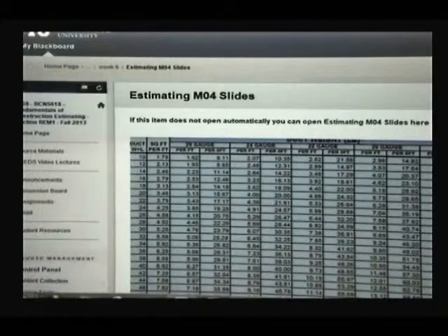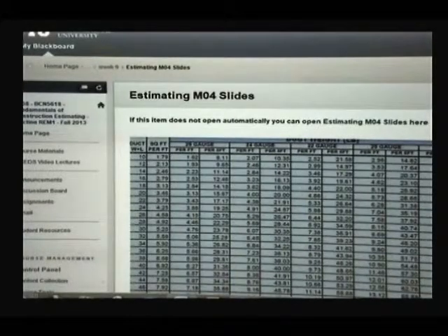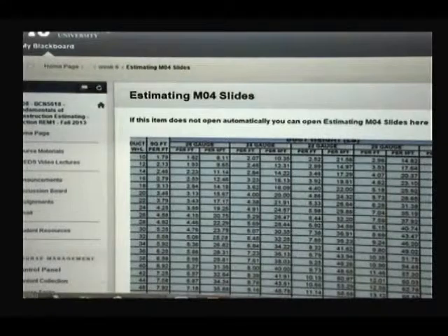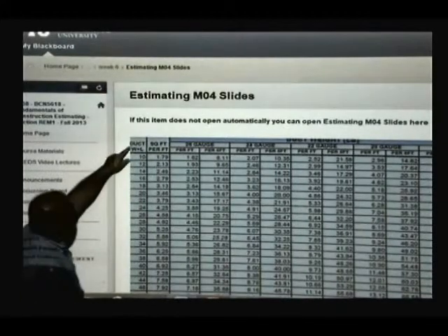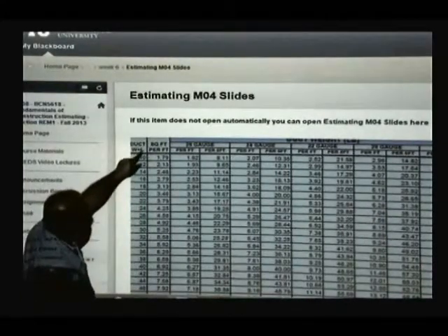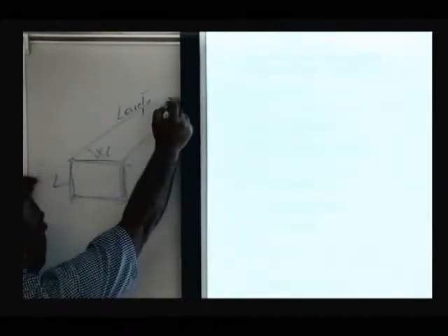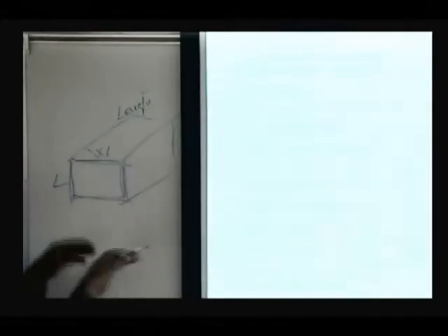So basically we have these two dimensions they call W and L, right? So we want to add W plus L, and then the table considers that that's times 2, right? Because the perimeter is 2 times this width plus 2 times this height, and then if we multiply by the length of the duct, this perimeter times the length will give us the surface area, right?